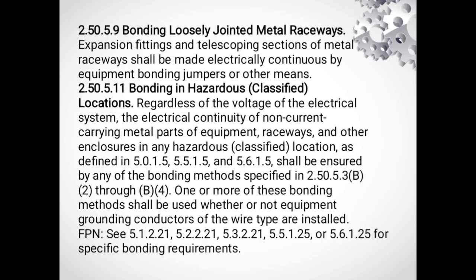2.50.5.11 Bonding in hazardous classified locations. Regardless of the voltage of the electrical system, the electrical continuity of non-current carrying metal parts of equipment, raceways, and other enclosures in any hazardous location as defined in 5.0.1.5, 5.5.1.5 and 5.6.1.5 shall be ensured by any of the bonding methods specified in 2.50.5.3b through B4. One or more of these bonding methods shall be used whether or not equipment bonding conductors of the wire type are installed.